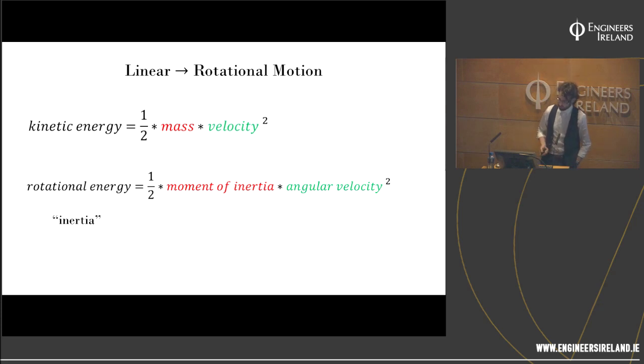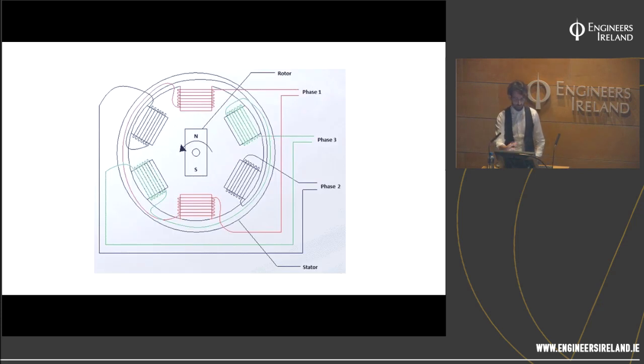If we drop back to our equation, we know that the angular velocity is related to the rotational energy of the machine. This angular velocity is connected to the grid frequency, so if the grid frequency changes, that angular velocity term will change, and hence we have a transfer of rotational energy to or from the grid depending on which way the frequency changes. This is just a consequence of the beauty of the design of a synchronous machine. It's pure physics. Now, not all power plants are created equal when it comes to inertia.